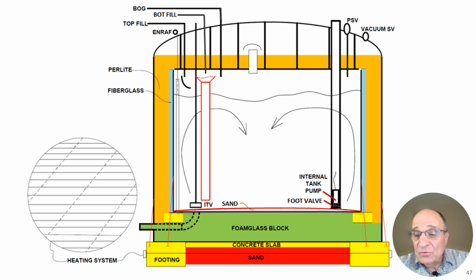And that for the inner tank, you have a footing. For the outer tank, you have a footing as well. And you have to have hold down straps so that the tank doesn't bulge upward when it's pressurized and it's got no liquid in it. If you pressurize it, let's say it has a very little amount of liquid, but it still has a differential pressure inside the tank, well, you don't want it to bow upward. And you also have to have these straps for seismic reasons. So they're built into the calculation for seismic reasons.